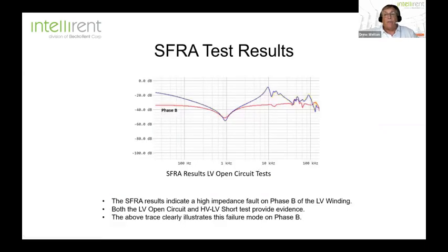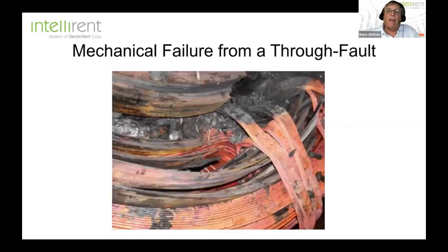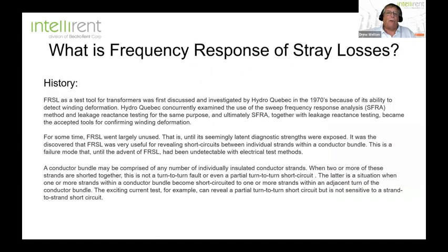Then we looked at the SFRA results, and you could see the high impedance fault on phase B of the low voltage winding, a clear indication during this test right here. And this is kind of what it looked like when they tore the transformer apart. It certainly wasn't pretty. And again, they didn't even consider that the problem existed until the differential relay tripped. And this would certainly create a differential trip.